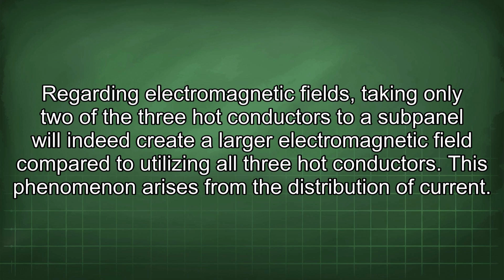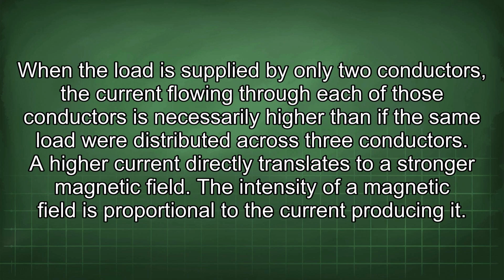Regarding electromagnetic fields, taking only two of the three hot conductors to a subpanel will indeed create a larger electromagnetic field compared to utilizing all three hot conductors. This phenomenon arises from the distribution of current. When the load is supplied by only two conductors, the current flowing through each of those conductors is necessarily higher than if the same load were distributed across three conductors. A higher current directly translates to a stronger magnetic field. The intensity of a magnetic field is proportional to the current producing it.